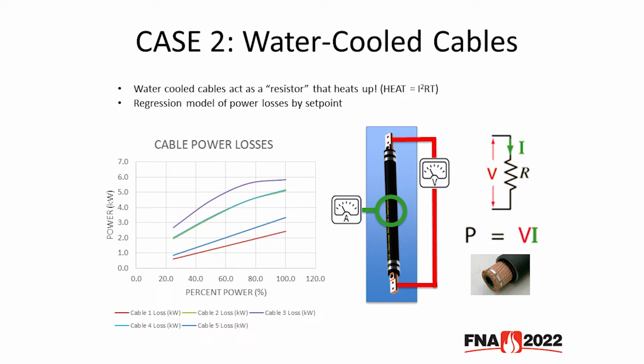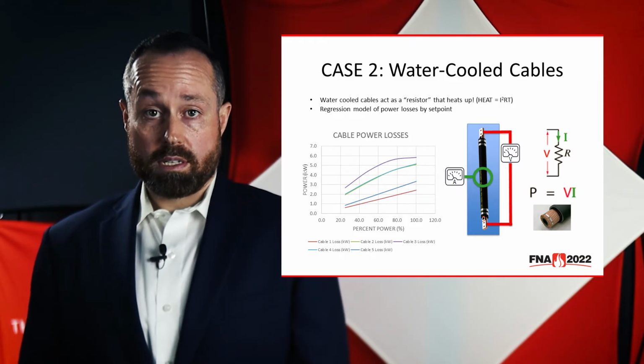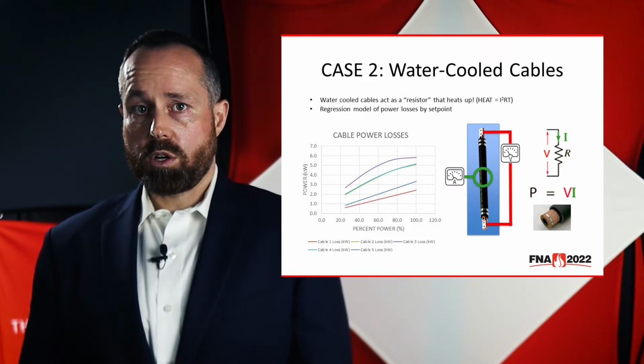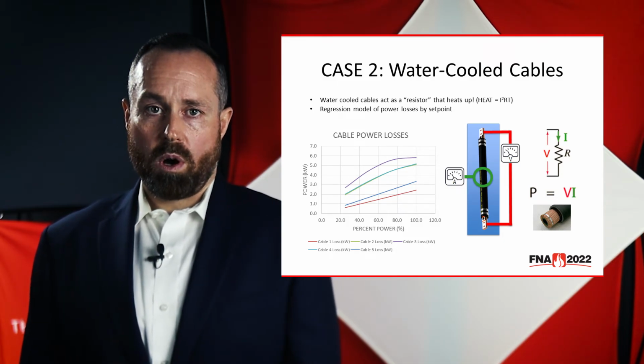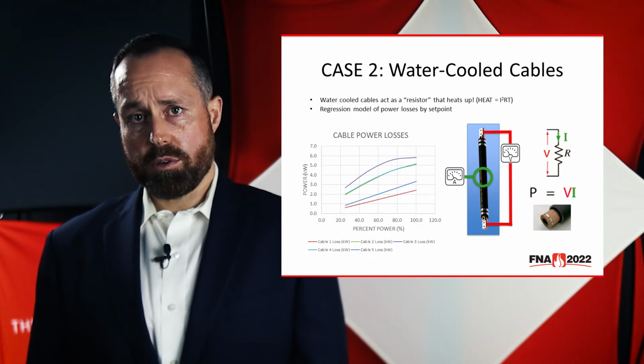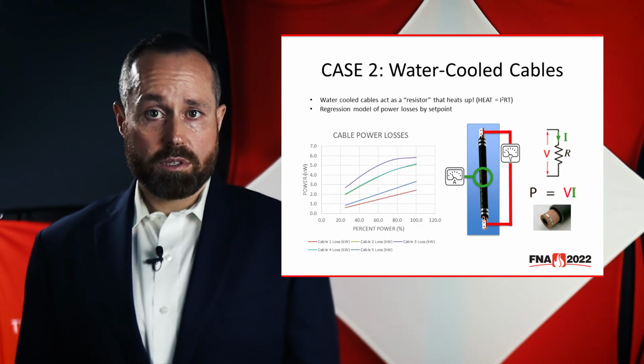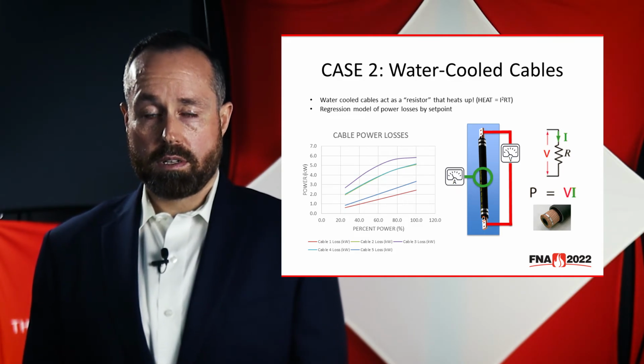The graph here shows the cable power losses by percent power. The purple line, for example, shows that at 80% power, this cable is continually dumping 5.5 kW into the water, whereas at 40% power, this cable is only continually losing 4 kW. Remember that everything after the transformer is essentially a heating element. Water-cooled cables are just a resistor wrapped in water. This introduces the value proposition of reducing this high current circuit outside the furnace to improve electrical efficiency.